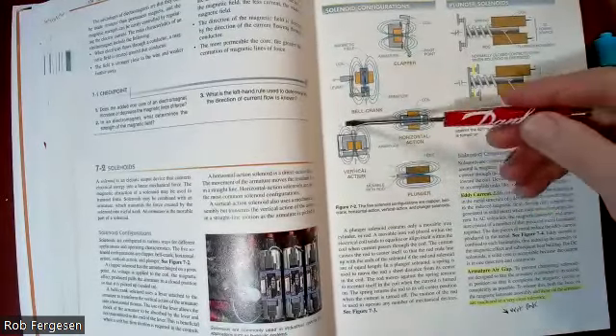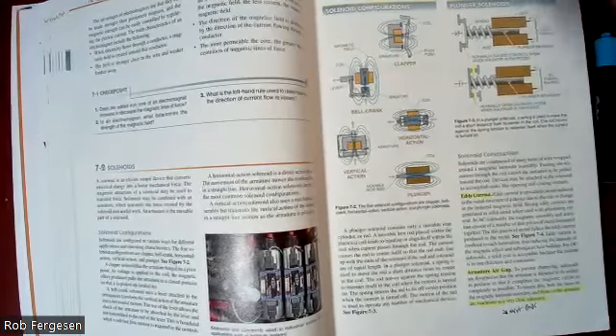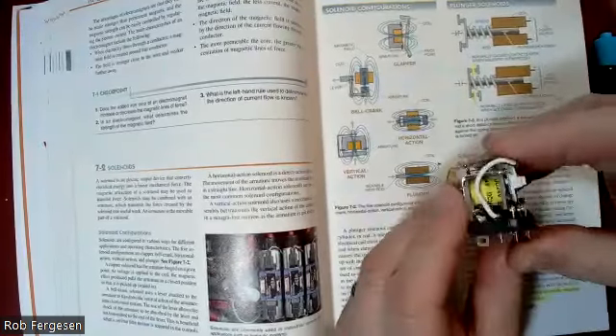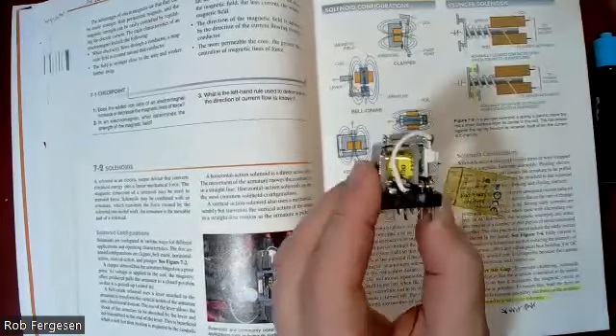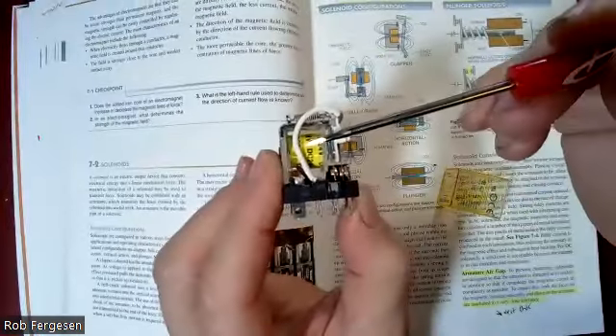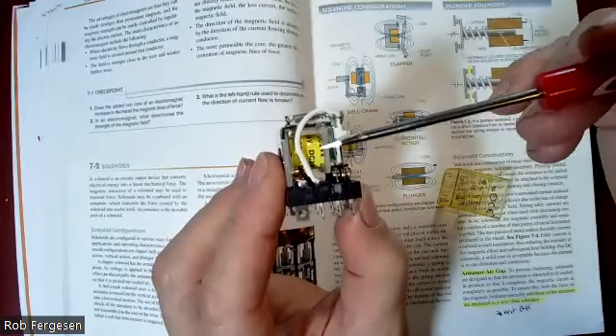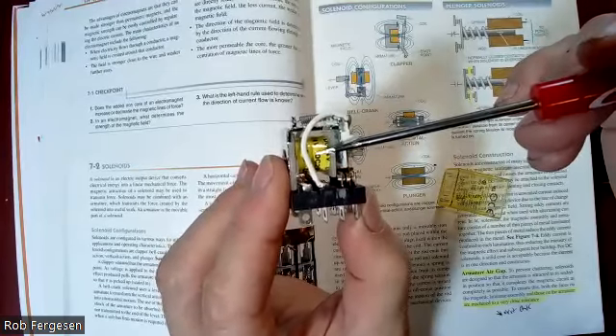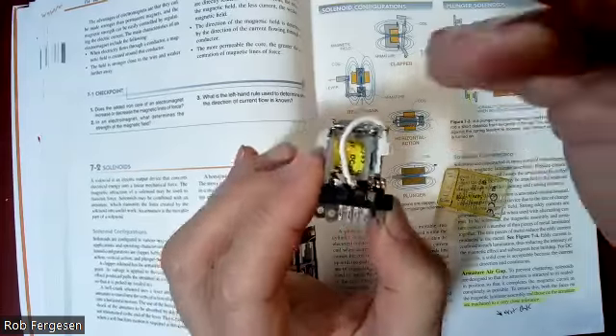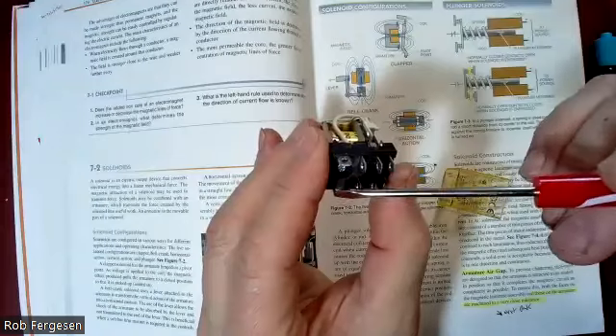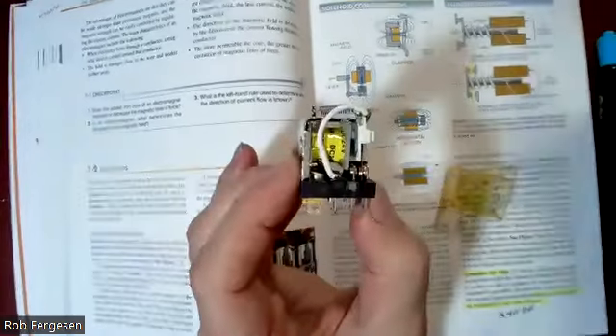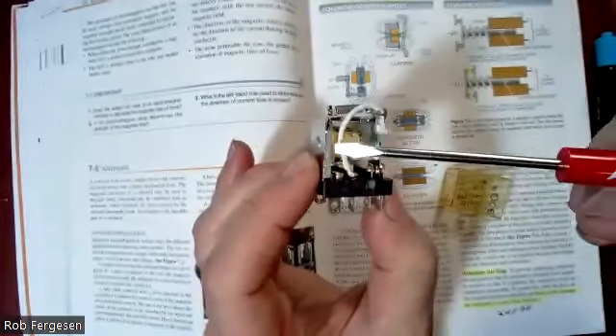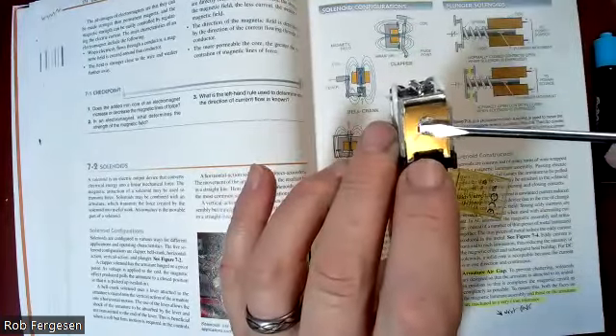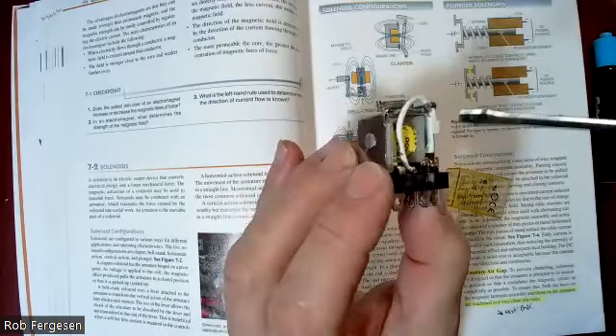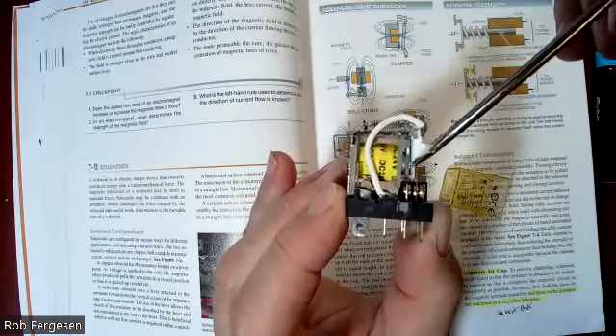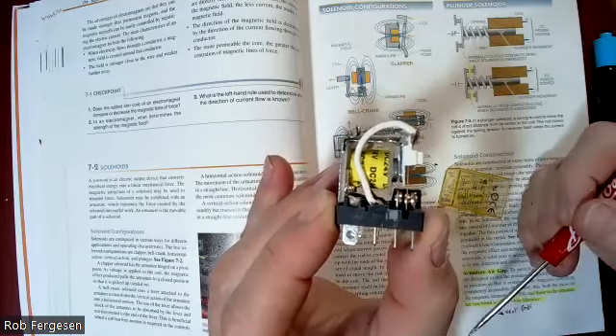That's a vertical action. On this particular relay, we've got another coil right here. This little thing that's wrapped in yellow tape is also a copper coil of wire. It's got two contacts that go down to these two leads on the base plate. If I give it DC power, the other one was AC, this one's DC, it actually creates the electromagnet, and there's a little steel core. You can see the end of the core sticking out of this. The front of the core is right there. You can see it just peeking out from the front of that coil.